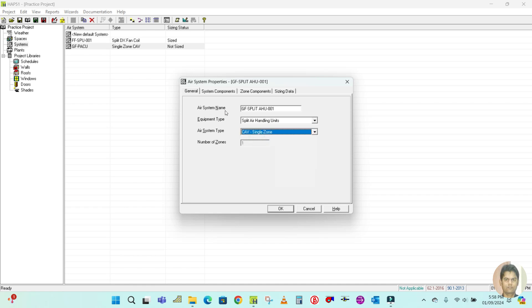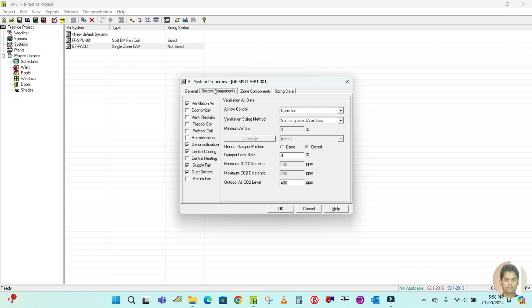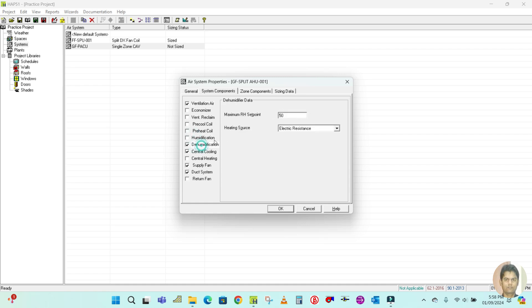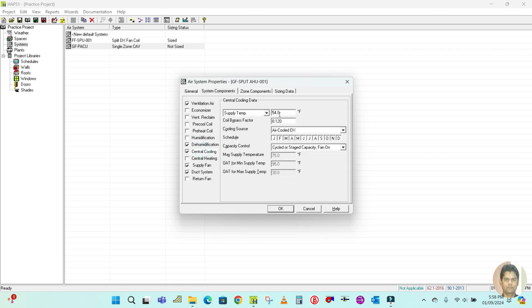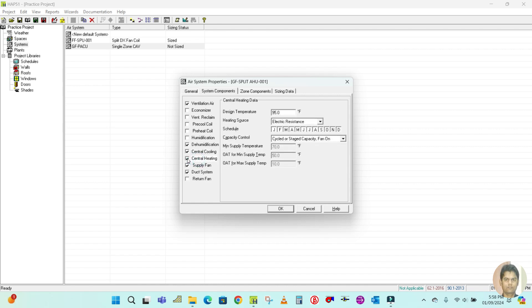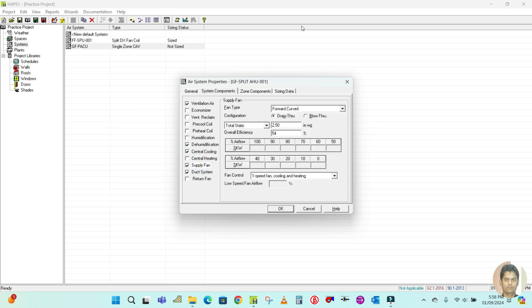Go to the system tab where you can see ventilation, economizer, ventilation reclaim, pre-cool coil, pre-heat coil, and many more options. The ones already ticked are mostly what we use. Humidification and dehumidification is set to 50 to 60 percent, which is fine. The central cooling coil is 54 degrees Fahrenheit. If you want heating you can select it here; if not, just uncheck it. Then click on supply fan.